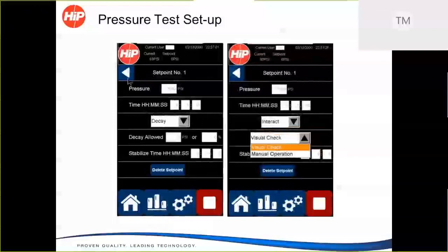So what that'll do is, again, allow you to drive to a pressure for a certain amount of time, but it's going to do a decay test. So we're actually going to run up to that pressure, and when we hit 5,000 psi within 1%, we're going to turn off the air to the pump. So we lock the system down, but we're not artificially maintaining pressure. So if you have a leak in your system, you're going to see that pressure decrease over time.